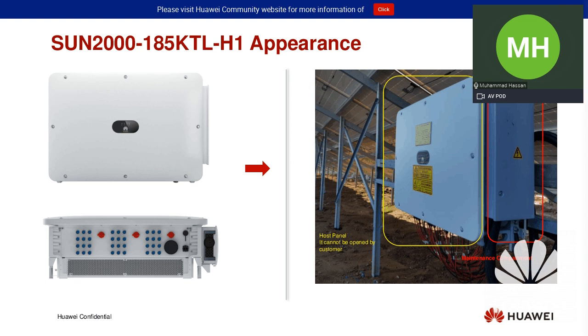Appearance: 3 DC switches you can see at the bottom of the screen, and all these 3 DC switches are controlling 3 MPPTs for the inverter. So in total there are 9 MPPTs, and 3 MPPTs are controlled by each of the 3 DC switches. On the right side, in the yellow part, we call this the host panel, which customers are not allowed to open. This is also the DC compartment where you connect the DC strings coming from the solar panels. Further right, in the red marked area, is the maintenance compartment, also called the AC side of the inverter, where you will install the AC cables and generate power from there.